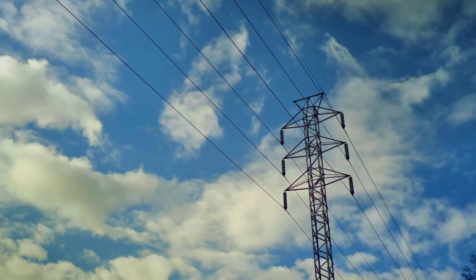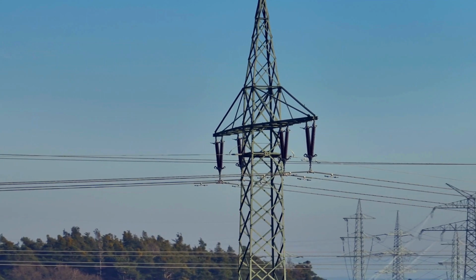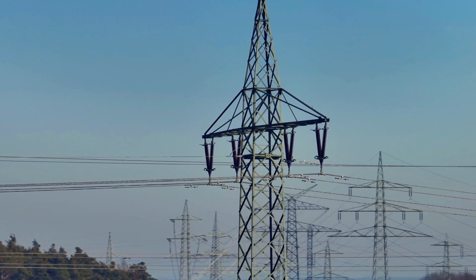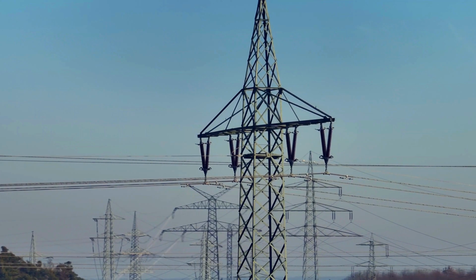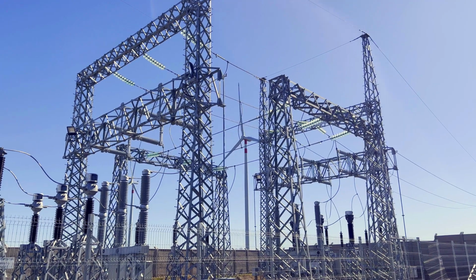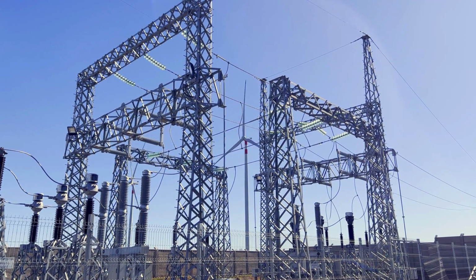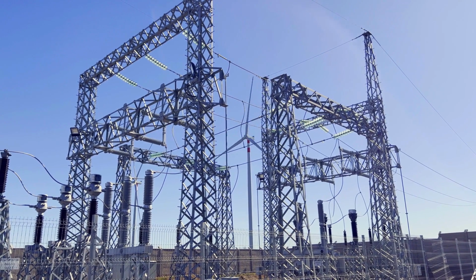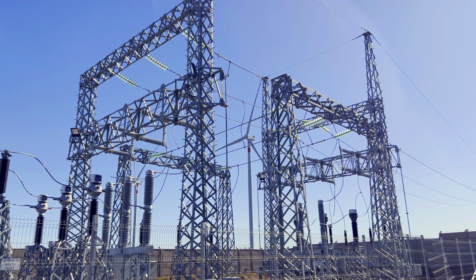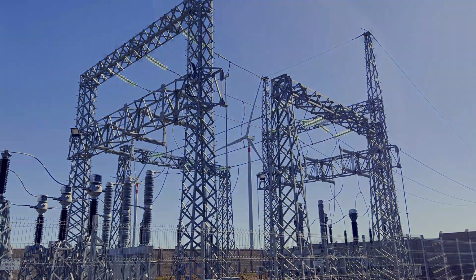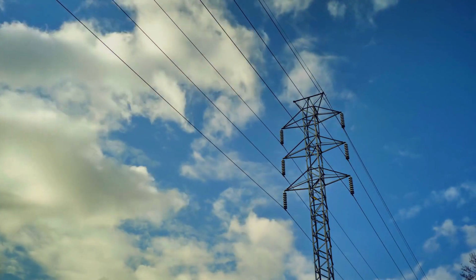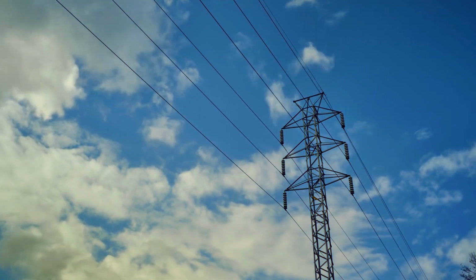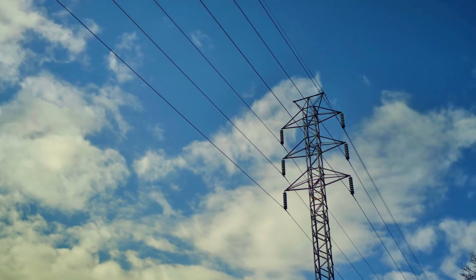Reactive power is the third thing. Synchronous generators naturally absorb or produce reactive power based on their field excitation, automatically, continuously, as voltage conditions across the system change. This is what keeps voltage stable across hundreds of miles of transmission. Inverter-based resources can provide reactive power, but it requires deliberate design and deliberate control. It doesn't happen by default, and it trades off against real power output. You can't always fully maximize both at once.